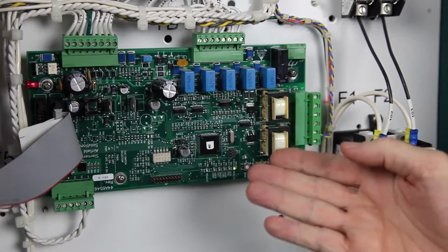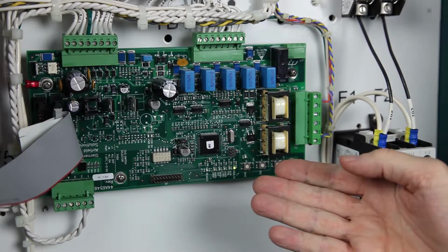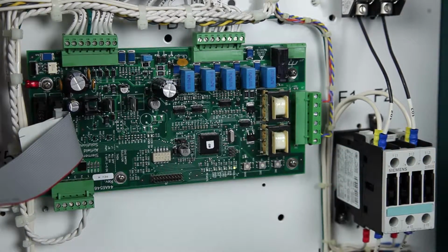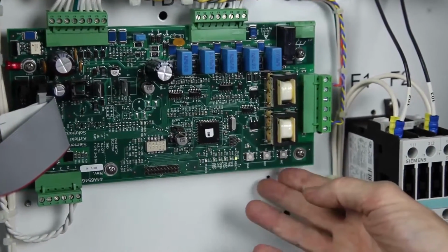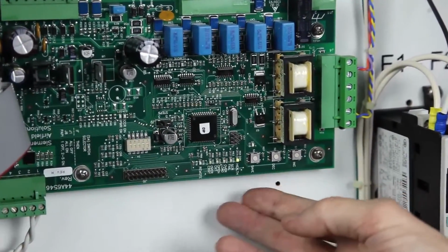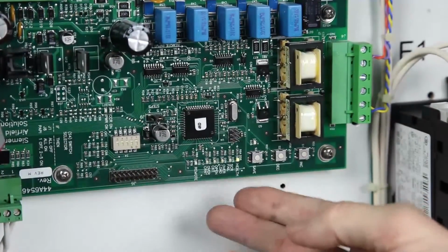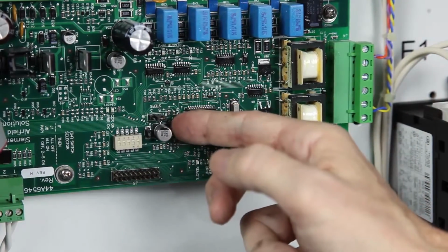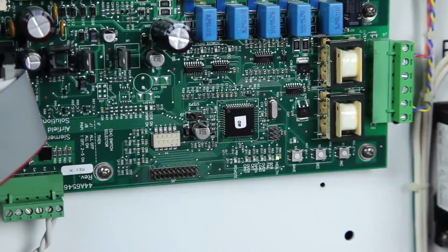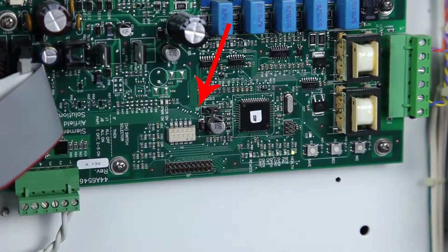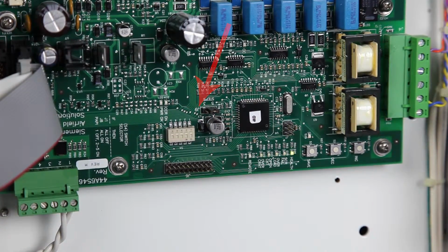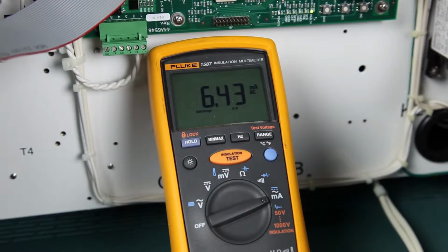Controller board 44A6546 has 3 buttons for calibration. They are marked increase, decrease, and save. Also note that there's a jumper on the board, J9, which sets the regulator as either a 3-step or a 5-step. Next, we're going to calibrate the high step setting.